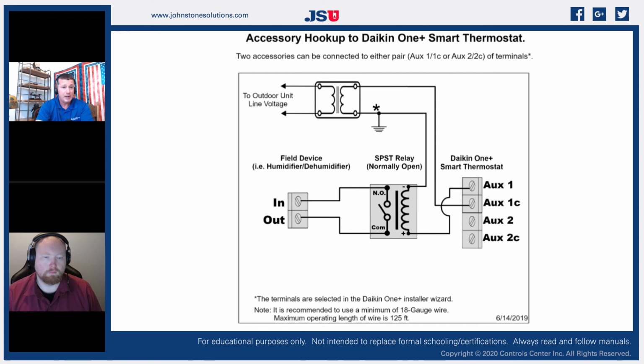Also be very aware that on any communicating network, it all comes back to making sure that those systems are properly grounded. A lot of our external and aftermarket components like powered humidifiers and powered dehumidifiers have isolated power sources, right? They have their own power. They're not always grounded. So if you tie a powered accessory into a communicating system, those relays on the Daikin 1 Plus particularly, it's got 2 sets of auxiliary contacts that you can use. Those are not true relays. It's solid state circuitry through transistors and diodes basically. So it's not an actual gate switch.